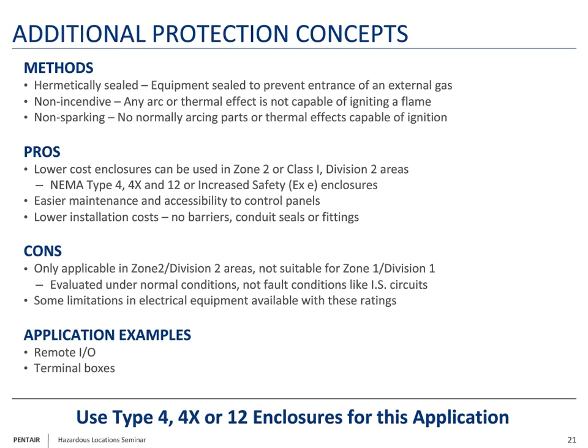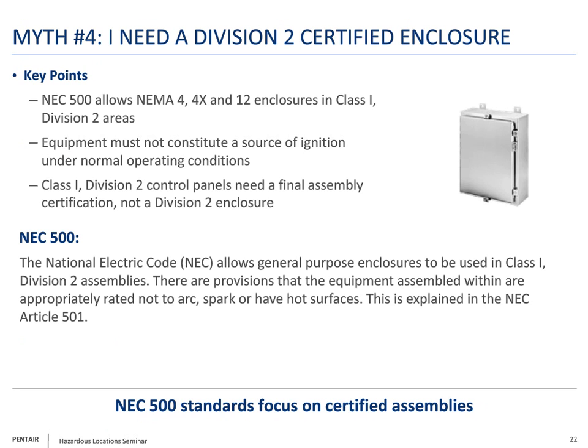When we see these applications in Class 1 Division 2 or Zone 2 areas, especially Division 2, we get requests saying, I need a certified Division 2 enclosure. And there's no such thing as an empty enclosure that is certified for Division 2. What the NEC 500 standard says is that for Division 2 areas, NEMA 4, 4X, or 12 enclosures can be used in those environments so long as the equipment installed in them does not constitute a source of ignition under normal operating conditions.